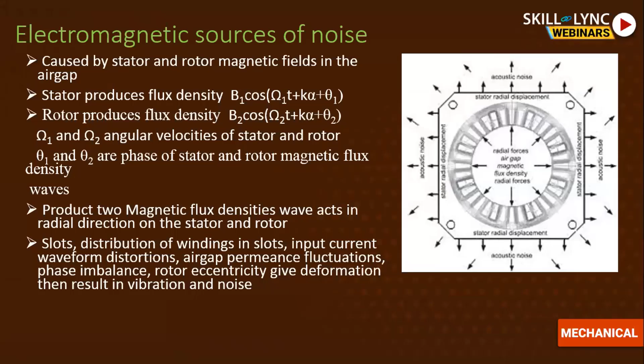As we discussed, the magnetomotive forces and magnetostrictive forces travel radially. About 50% of magnetostrictive forces and all the magnetomotive forces travel radially and create a higher harmonic force and torque in the motor. Then the stator frame, there is a frame outside the stator, is radiated. If it has a natural frequency coinciding with the frequency of the radial force, then the noise is amplified.